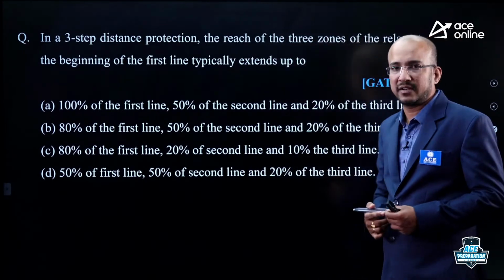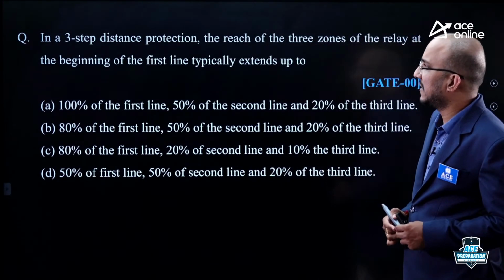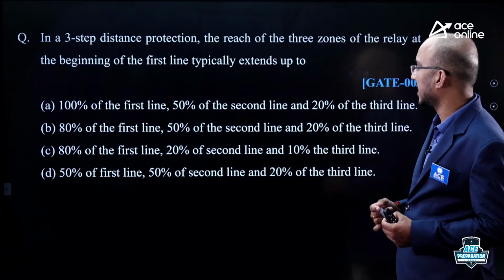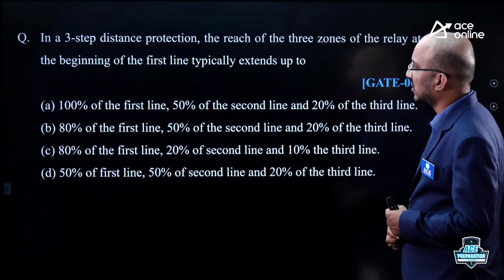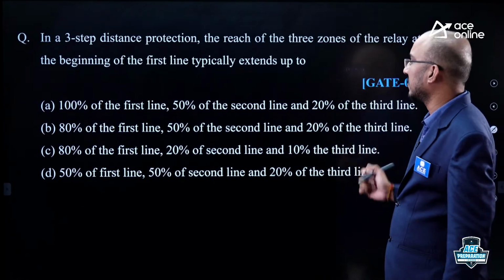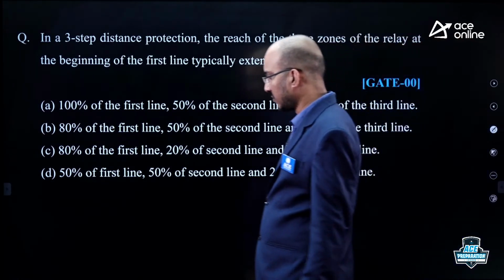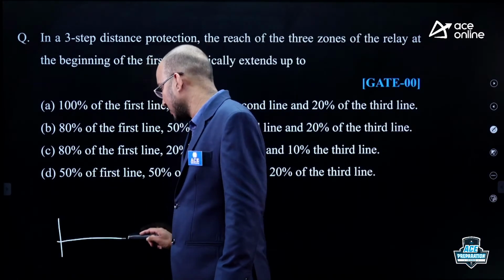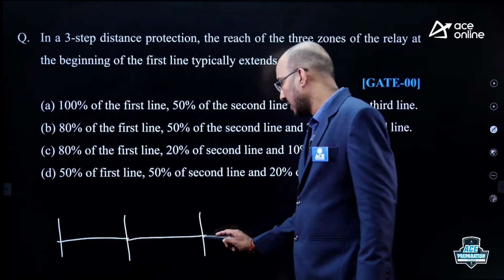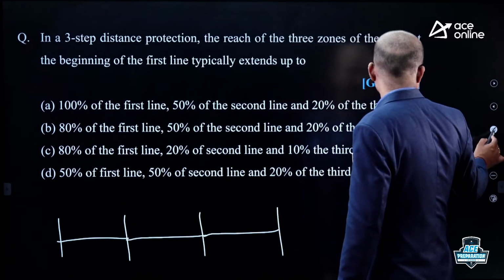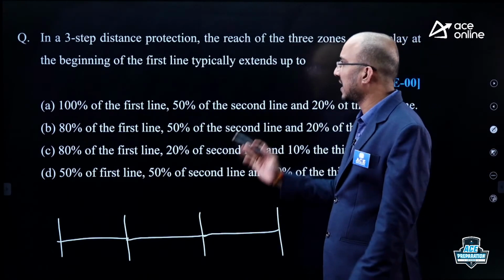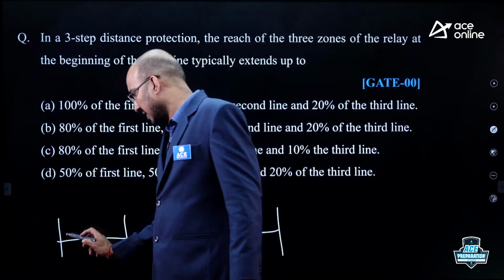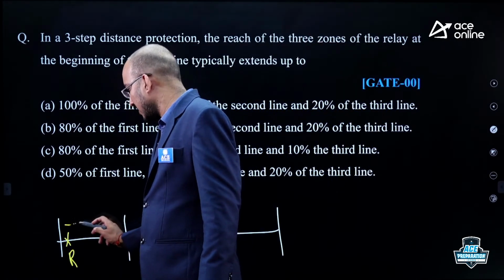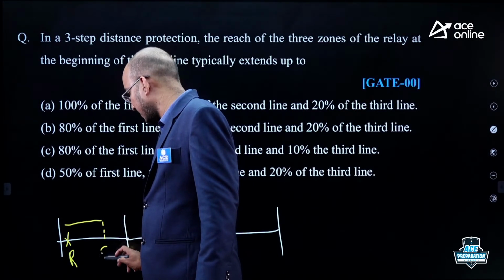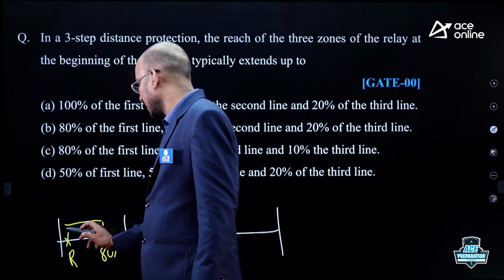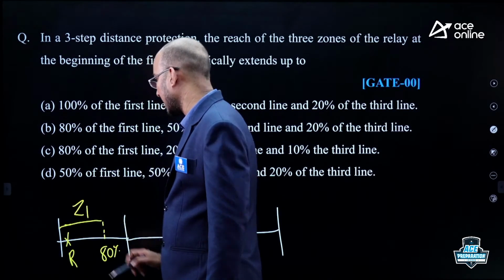Now let us observe this question. In a 3-step distance protection, the reach of the 3 zones of a relay from the beginning of the first line is typically extended up to what? If you go for the analysis of the zonal protection scheme in a 3-step protection, there are 3 sections. The relay is placed here. So the first zone will be up to 80% of the first line. This corresponds to zone 1.